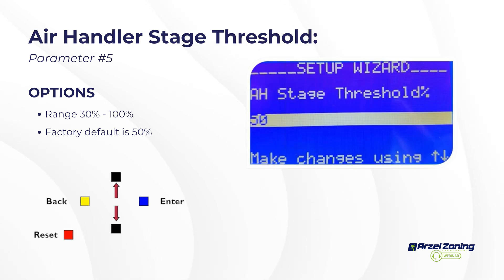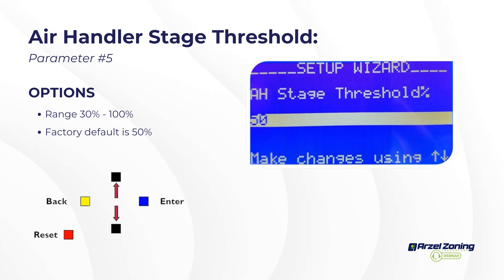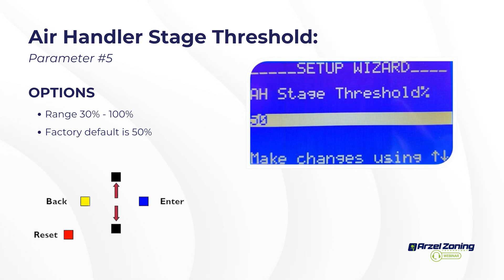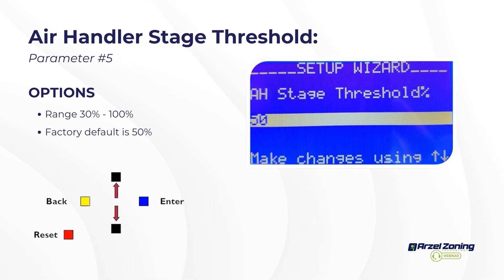The air handler stage threshold works closely with zone weighting — once the sum of active zone weights meets or exceeds the threshold, W2/Y2 outputs to the furnace or air handler are allowed. The Y2 air handler output happens right away, because the system needs to deliver as much airflow as possible to the open ductwork, so you instantly get Y1 and Y2 going to the furnace air handler.